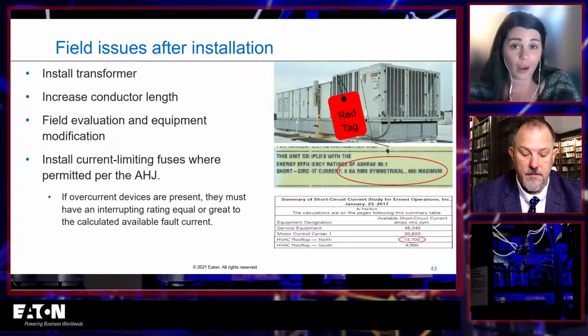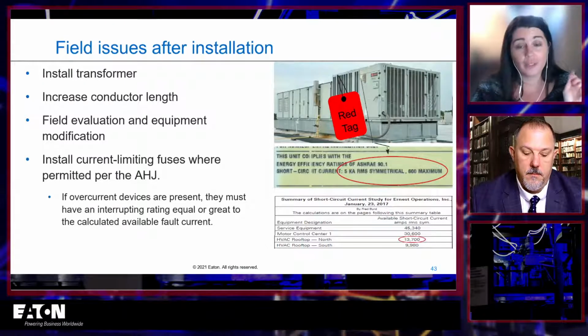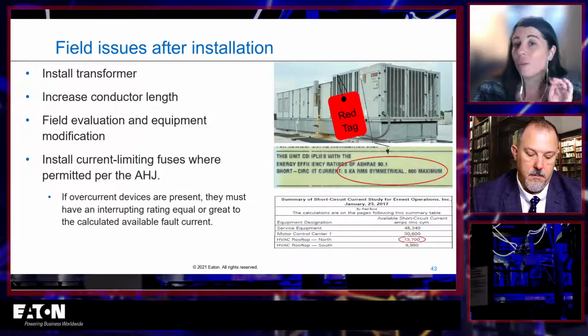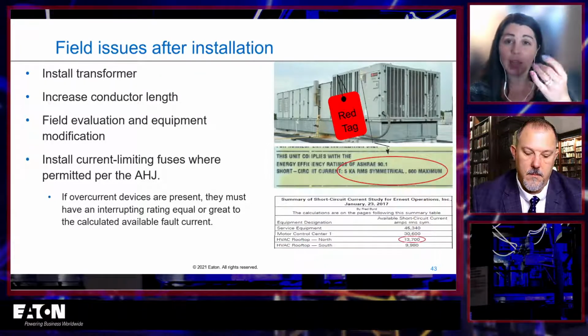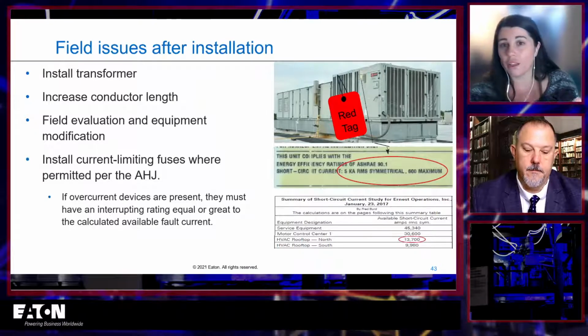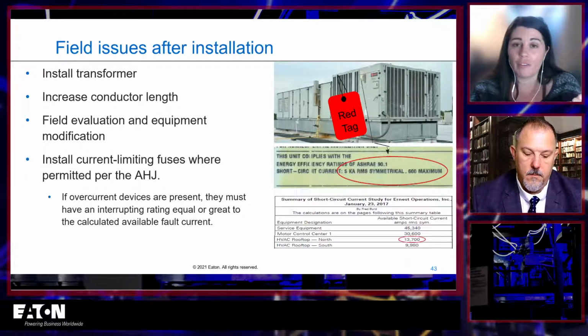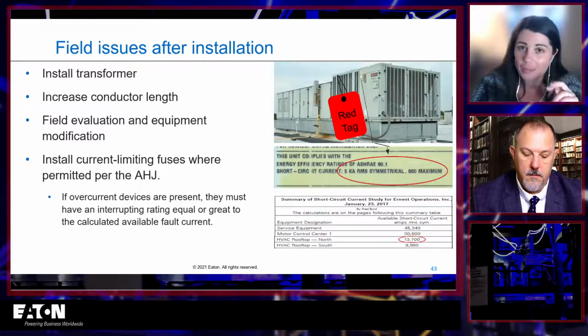It'll technically work, it'll pass code, etc. But I don't prefer it as a solution. I'll just put it that way. You can also install something like a line reactor too, right? A line reactor can also drop the available fault current in front of it. Those are just usually more expensive and with longer lead times. So you almost never actually see them being used as your method for that reason.